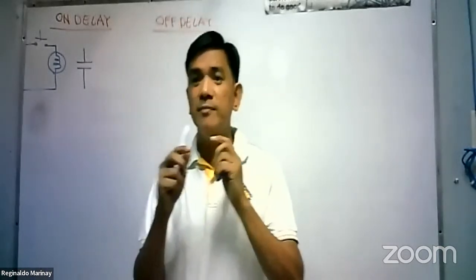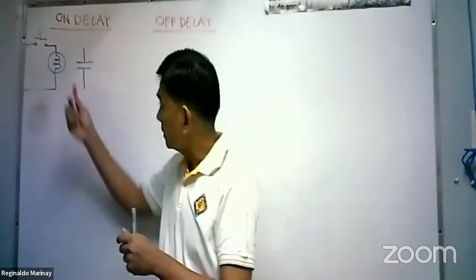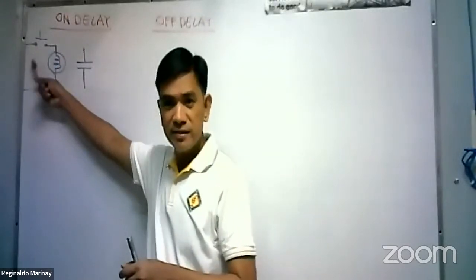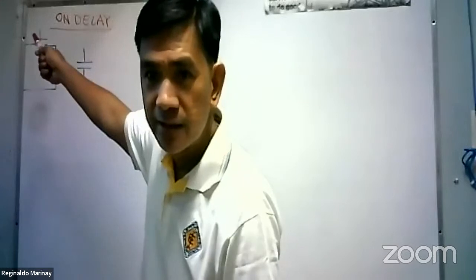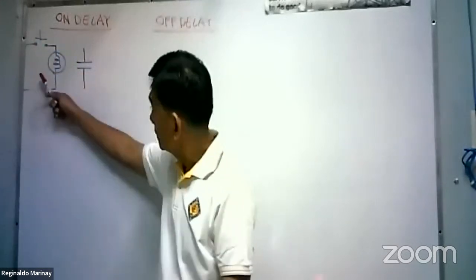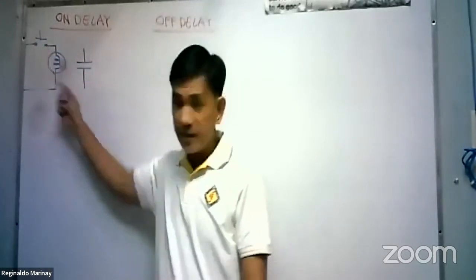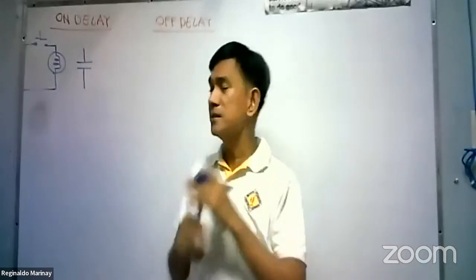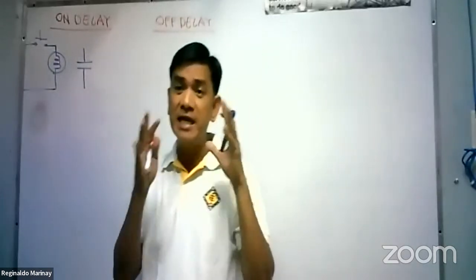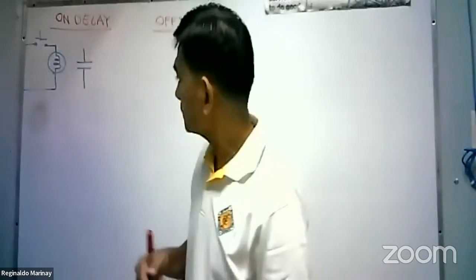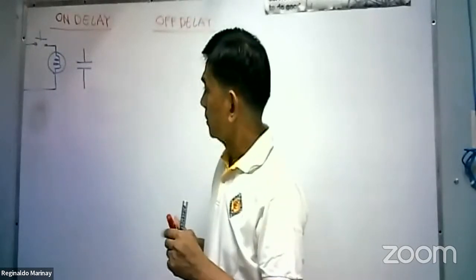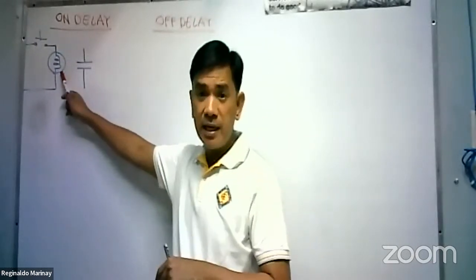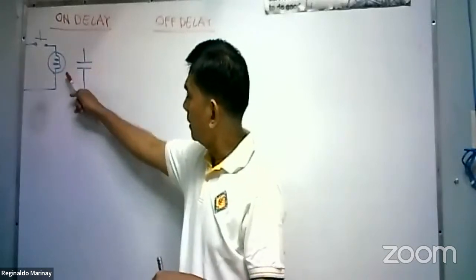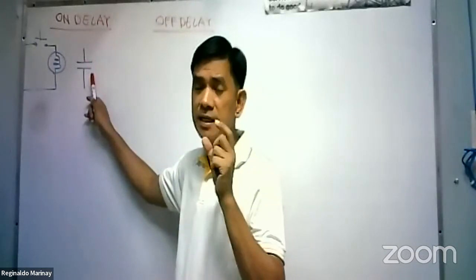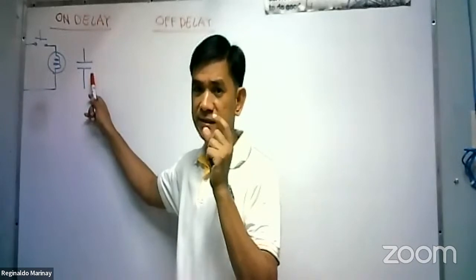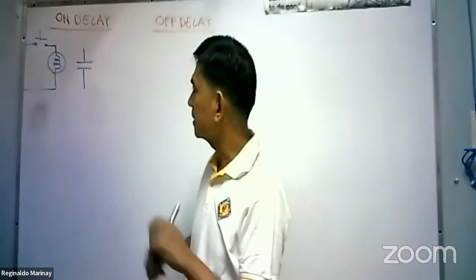Okay, for example, we have a push button here. So when we see this one, makikita ba nila? Okay, I hope you're seeing our simple diagram. This is the basic difference of the on delay and off delay timing relay. Okay, so this is the holding coil of the timing relay, and I will use first our normally open contact.